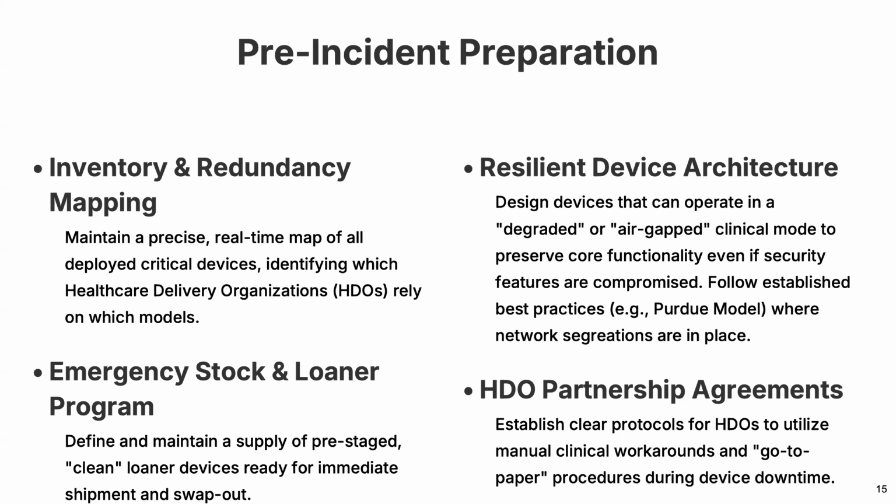So have an understanding, a real-time map of all deployed devices, and identify which of your customers, which HDO, relies on your devices, which version, which model, because not all incidents affect all versions. So you can filter your communication down to what is really relevant.